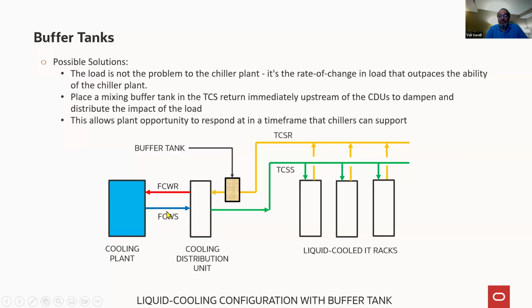That thermal storage can be here in the facility cooling water. If the chiller plant serves many other customers in the colo facility or any other data center, it's possible to actually put it downstream of the CDU also. It will be a smaller one because then it's sized just for the CDU loop. But you can put it here or here, it doesn't matter as long as it's in the supply side. I'm not going to talk about thermal storage anymore. I'm going to talk about buffer tanks.